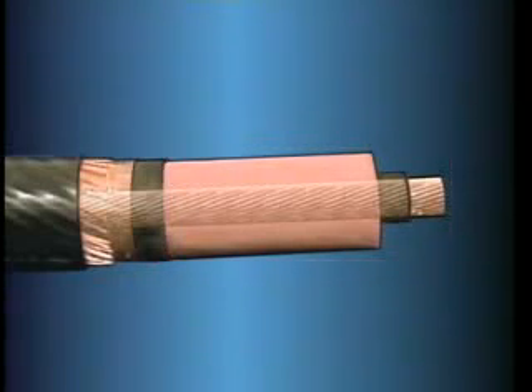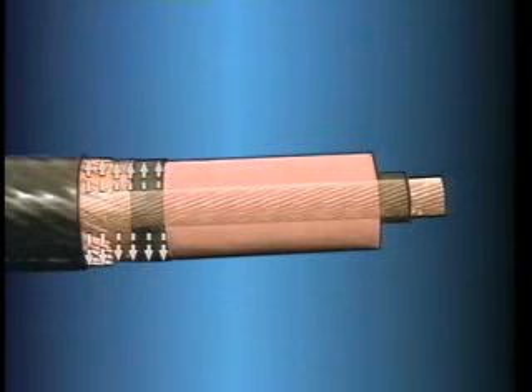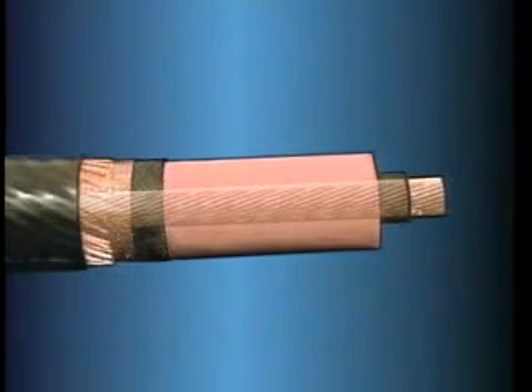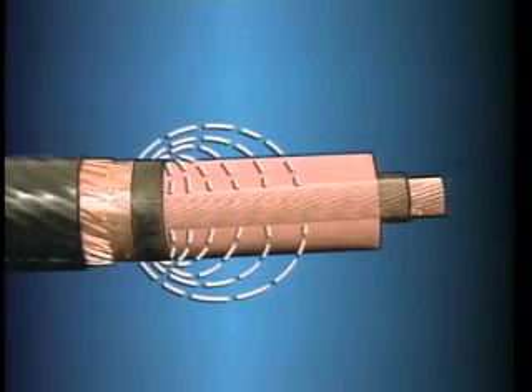Where the shields are intact, the voltage stress is evenly distributed through the insulation so that it's not concentrated in any one area. However, where the shields have been removed, the lines of voltage stress curve back and concentrate at the points where the shields end. Without some means to control this stress, the insulation could break down, resulting in a cable failure.